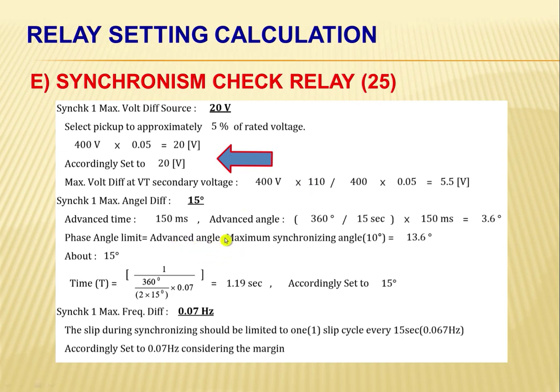And the advanced angle we have to calculate is 360 degrees over 15 seconds times the 150 milliseconds advance time. This 15 seconds is during synchronizing, wherein one slip cycle has to occur every 15 seconds. So the phase angle limit, the total, is 13.6 degrees. To round this off, that's why we have 15 degrees for our maximum angle difference.